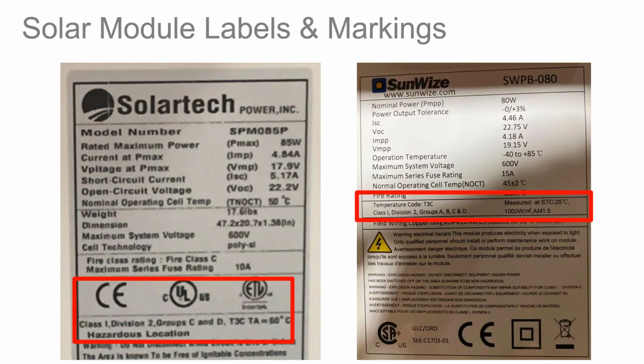All right, so as I was mentioning, in the solar module, the label, similar to the charge controllers, is basically mandated by these authorizing bodies to contain any certification information. So there's a wealth of info that you can find on a solar module label. And in addition to all the great core details around electrical parameters and series fuse ratings and so forth, I did want to point out that within this group classification, it's not a given that just because a solar module is certified to Class 1 Division 2, that it is so for all groups A, B, C, D.